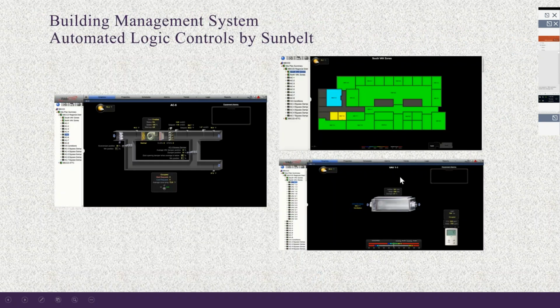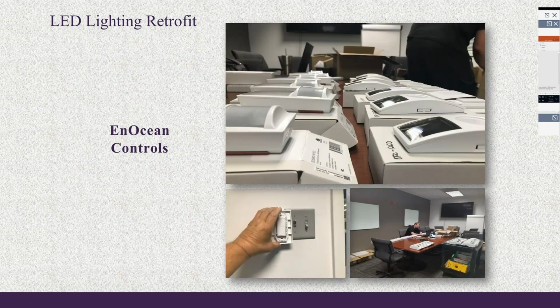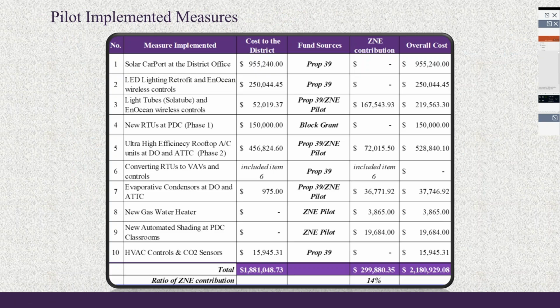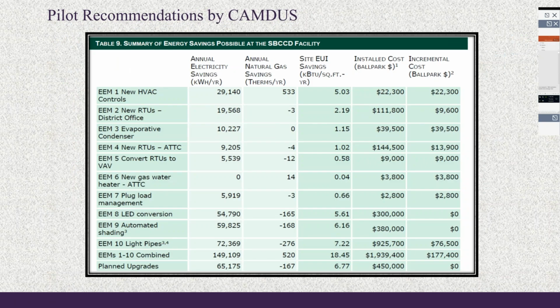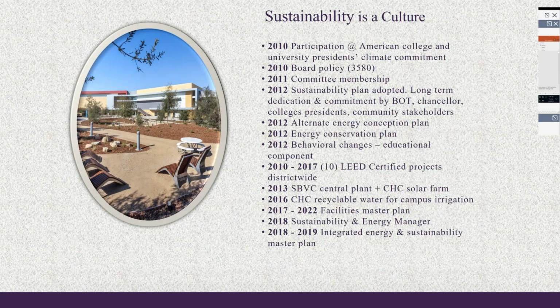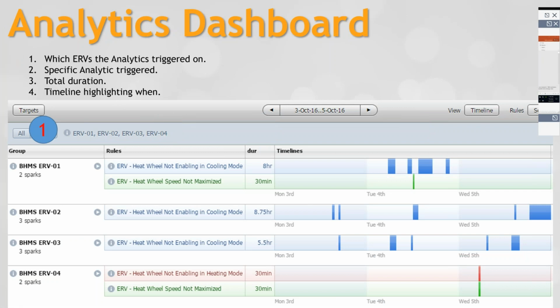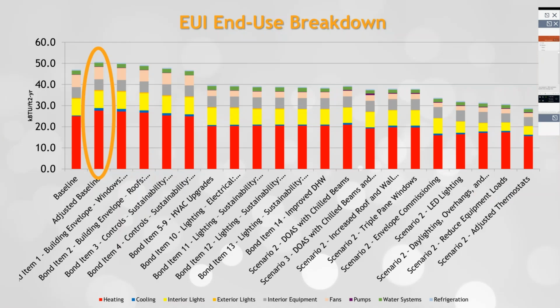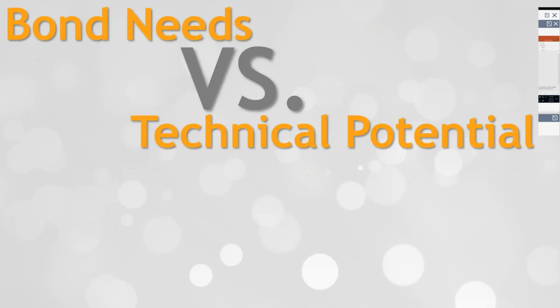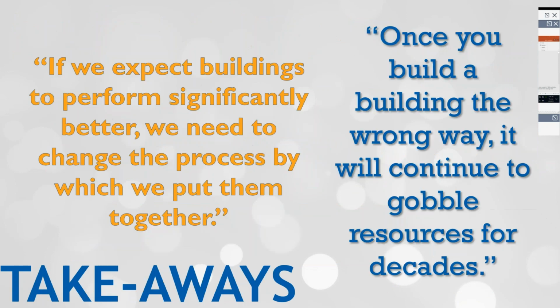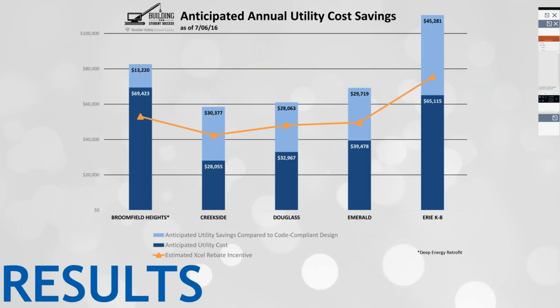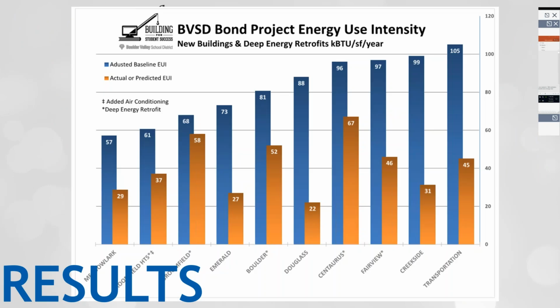Broomfield Heights Middle School, I think, was pretty dramatic. To get from 61 to 37, we gutted the mechanical system—pretty much packaged rooftop units—and put in a chilled beam system with dedicated outside air, with chilled beams throughout the entire classroom space, which really did provide a huge amount of savings. We also put in LEDs and some pretty good control strategies. Broomfield High School had a pretty limited project; we might argue that one isn't quite into the deep energy retrofit space, since we weren't able to touch as much of that facility. So the second one from the left is Broomfield Heights Middle School, 61 to 37, and the one next to it is Broomfield High School. We just weren't able to impact as much on that school with what we had for bond dollars—it's a big high school, so we only got to touch a portion of the building.